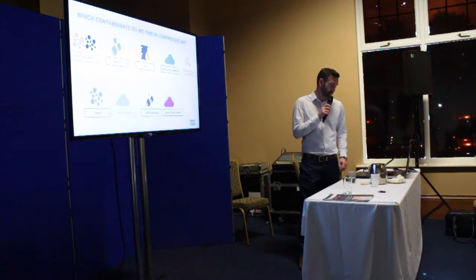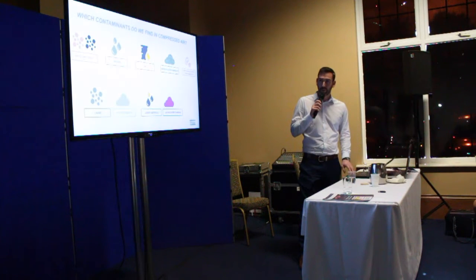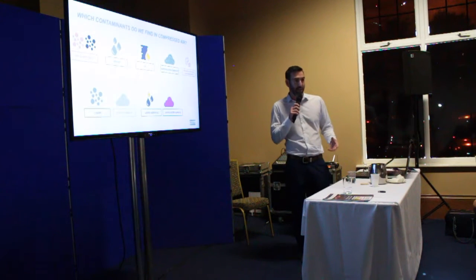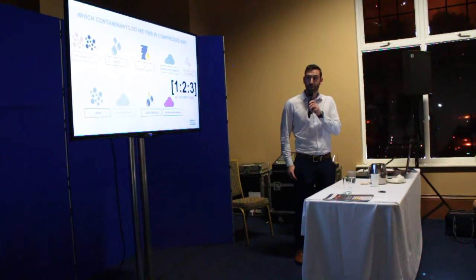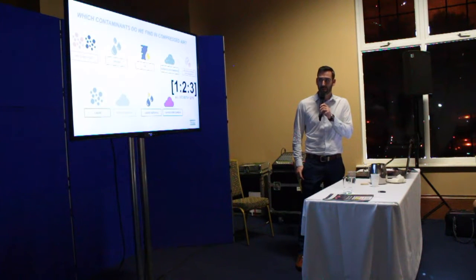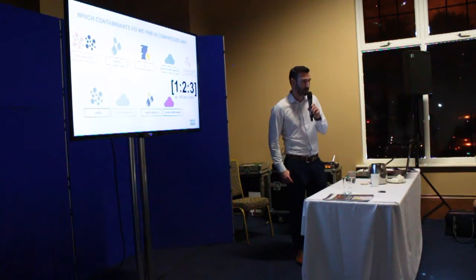So 8573 is the actual compressed air standard. It looks at the quality of the compressed air and what quality you want to achieve. To talk about quality, first we have to talk about the contaminants. As you see, there are 5 main contaminants in compressed air. There's your dust, dry and wet, your water, which breaks down into liquid and vapor, your oil, which also breaks down into aerosol and hydrocarbons, or liquid and vapor, your gas contaminants, this is your CO and your CO2, and your microbiological contaminants. These are your viruses and bacteria.